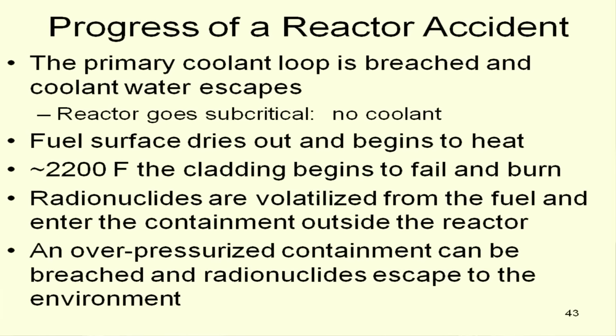And at that point, the fuel surface can dry out and begin to heat the surface of the fuel cladding. At about 2200 degrees Fahrenheit, give or take a little bit, the cladding begins to fail. And zircaloy cladding is pyrophoric, so you get it to a certain temperature, it begins to not so much burn with oxygen, but more react with water. Zirconium goes to zirconium oxide, with the other product being our delightful friend hydrogen, which I suspect you've heard more than you want about in the last couple of months.